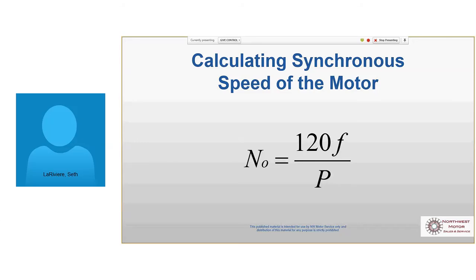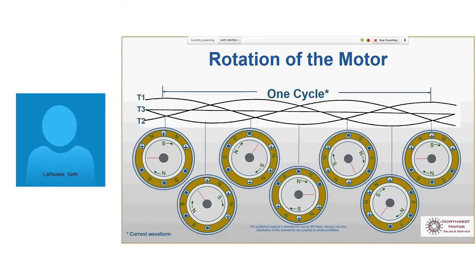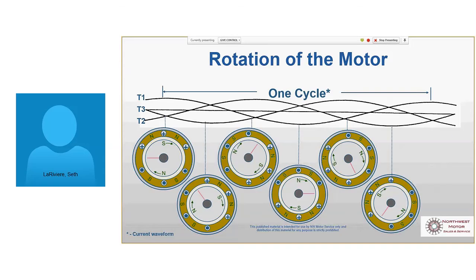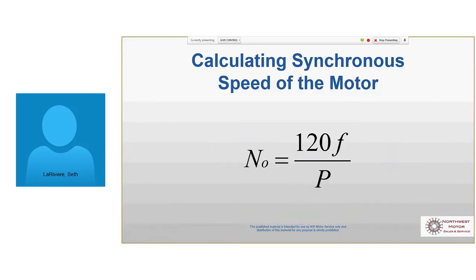And back on that previous drawing, well, too far to go back. You can see that last one had 3 groups of north and south poles, right? So that's the pole group that we're counting here. So if you divided all that out, 120 times 60 is 7,200. So the basic formula is 7,200 divided by the number of poles equals your RPM. So this is a 4 pole, 7,200 divided by 4 equals 1,800.